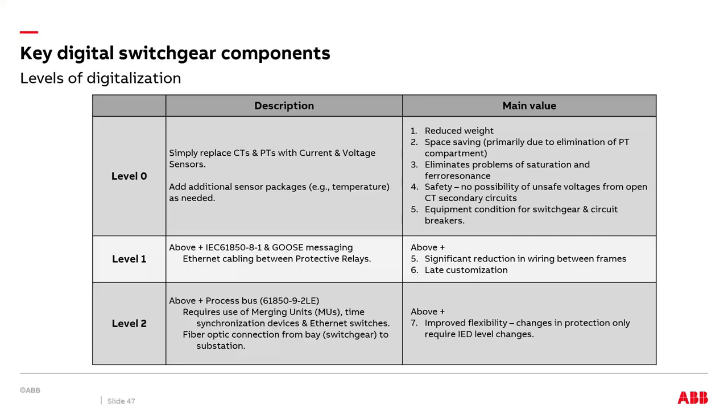And in this level, you can also use synchronization devices and Ethernet switches. You can also use PTP or IEEE 1588 devices and fiber optic connection from the switchgear to the substation. So this is improving flexibility and giving you so much more for your application. And you just need to change things on the IED because the relays are already sharing all the information that there is because of the sampled measured values.